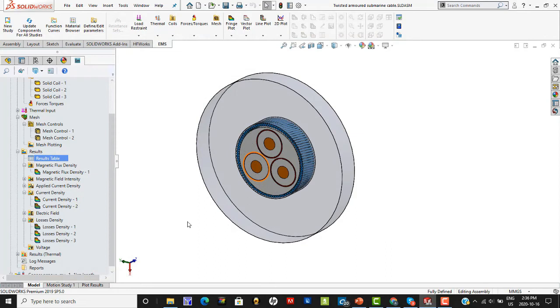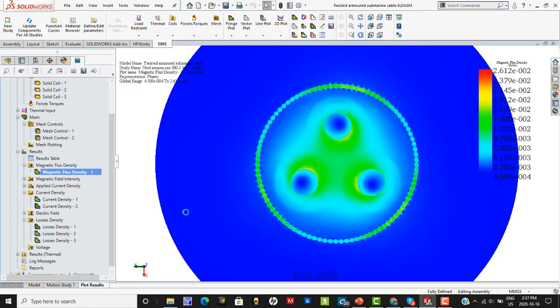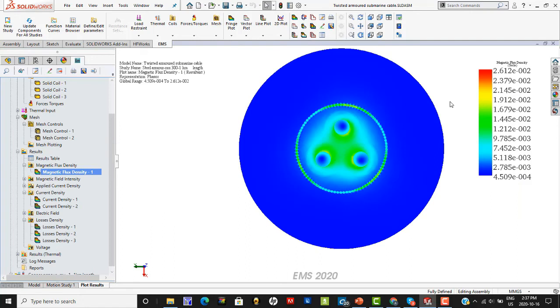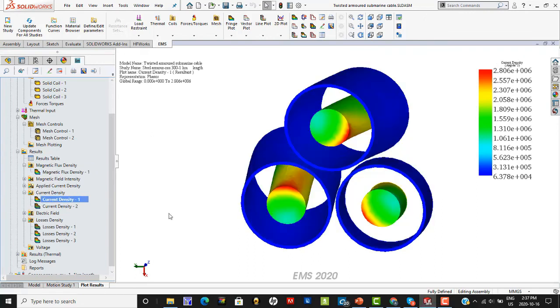EMS is 3D finite element software and hence has powerful 3D visualization. Users can visualize the magnetic flux density — here is a plot of the magnetic flux density in and around the cable. Notice that the steel armor provides an excellent shield to the magnetic flux density, so you can be assured that the flux density does not escape the cable. Next, we can take a look at the current density in the three cables and lead sheath — you can see both the skin effect as well as the proximity effect in this current distribution.